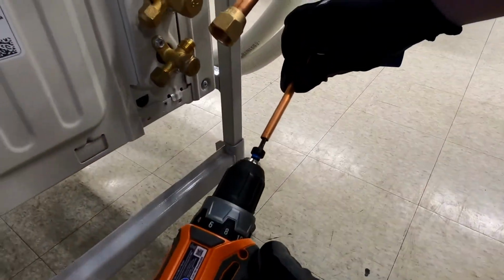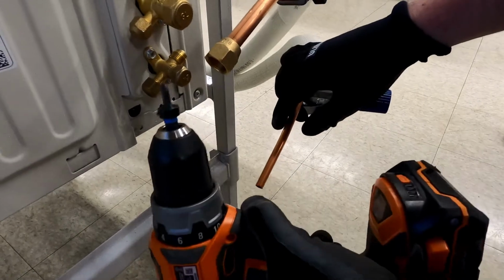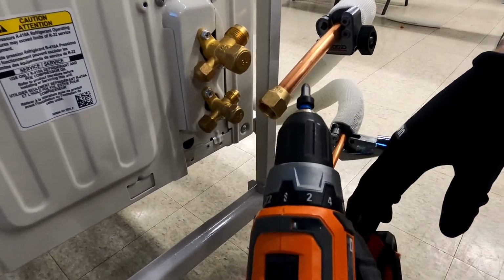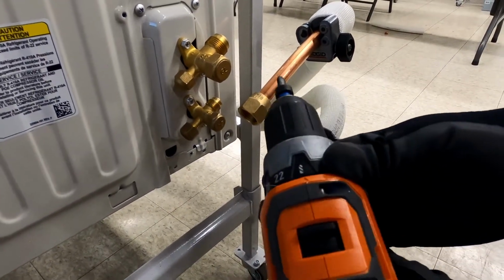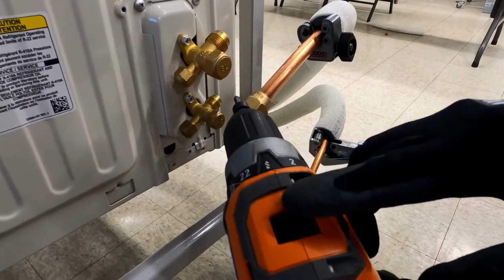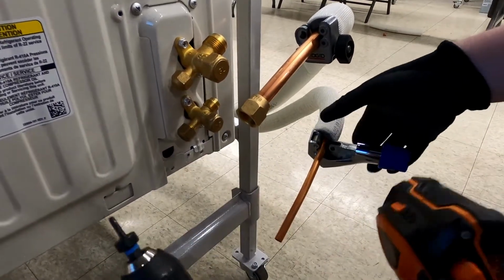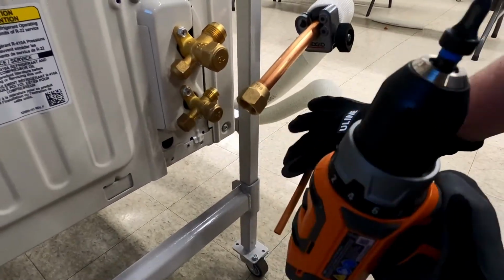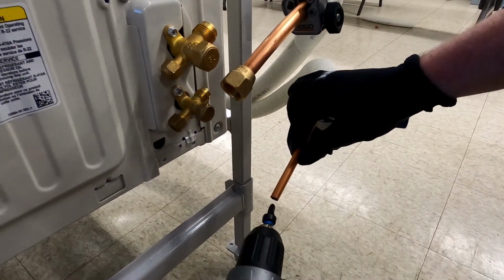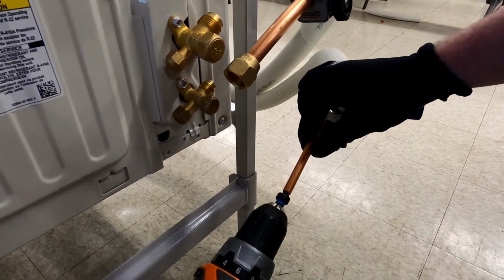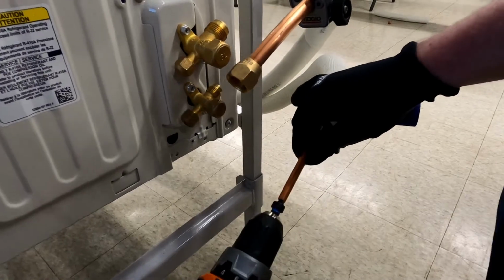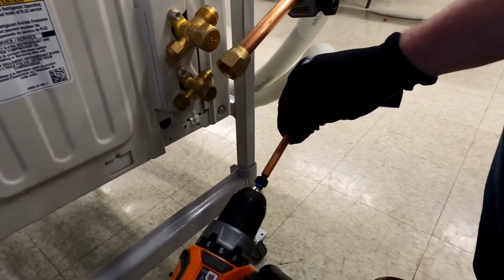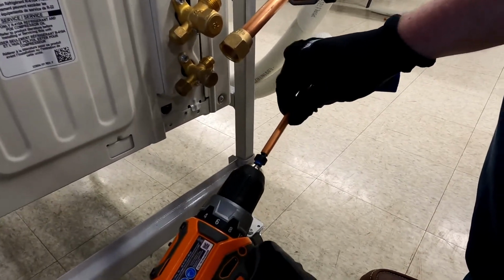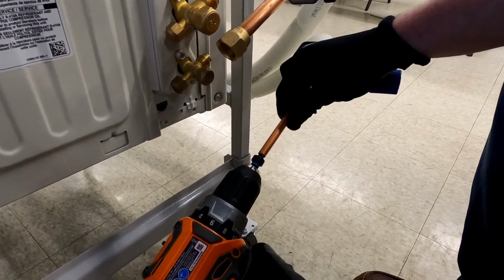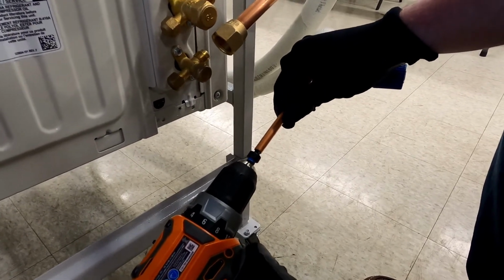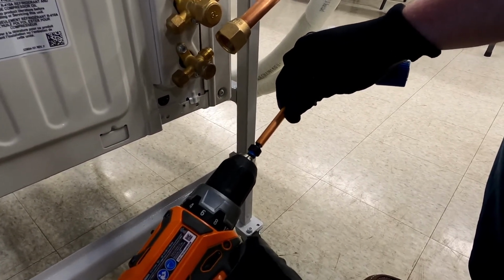All right, to make our other flare, we're going to use a flaring spin set. So you want to make sure that you have your drill set to full torque and the maximum RPMs if it's adjustable. Now, it's important that you wear gloves because the copper gets extremely hot, or some other form of holding the pipe. The keys to using this tool are to keep the drill perfectly straight with even pressure until you hit the stop, and then remove it while it's still spinning.